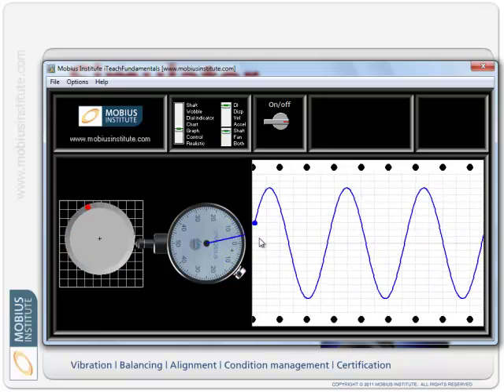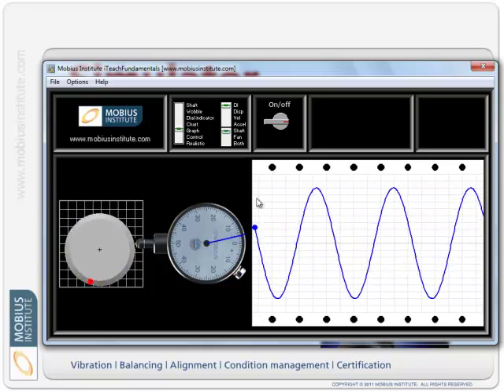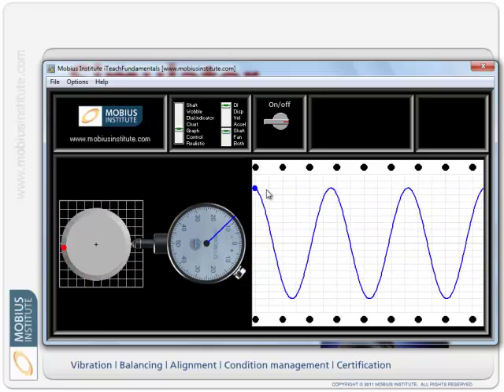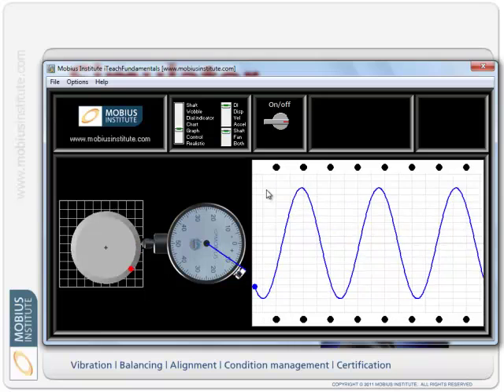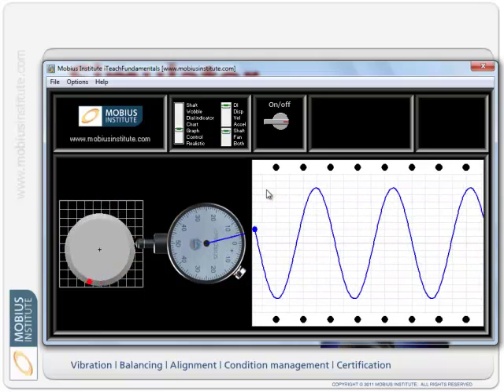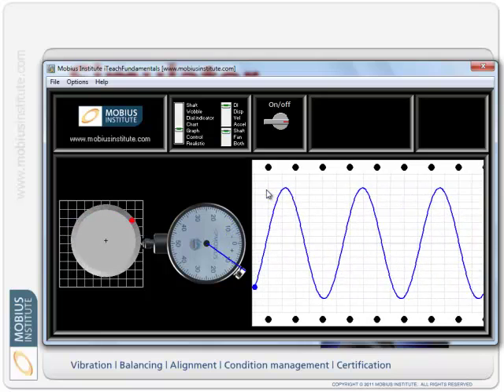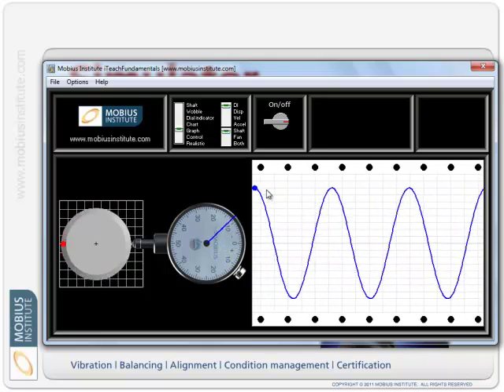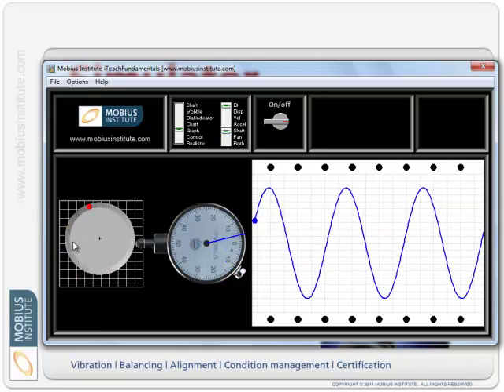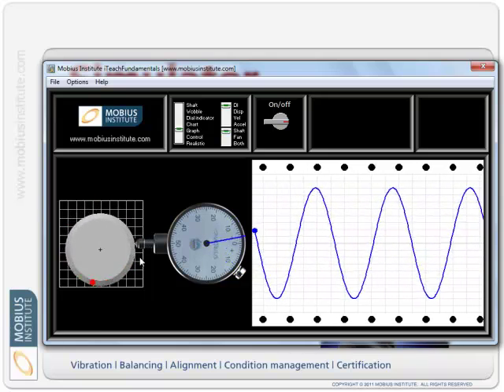That blue pen, which you can see, is still just moving up and down in line with the needle of the dial indicator. It leaves a pattern on the chart, and that pattern is called a sine wave. That waveform that we see there represents one single frequency, and that frequency corresponds to the rotating speed of this shaft. Now there are a few things we can do.